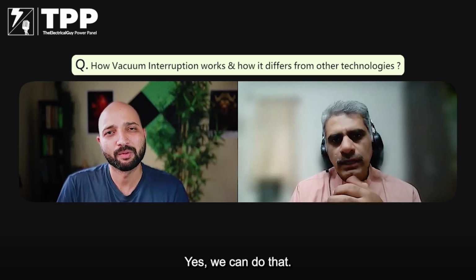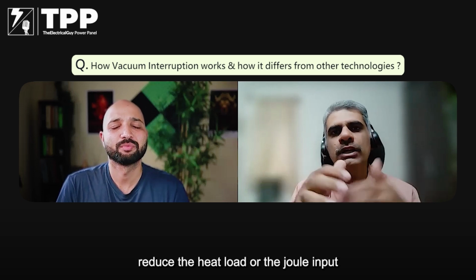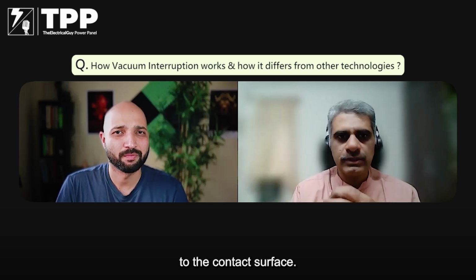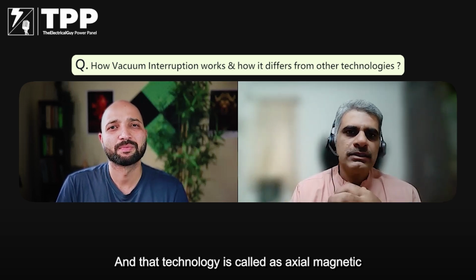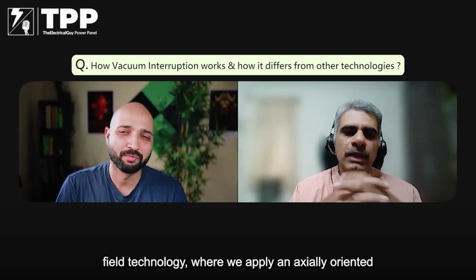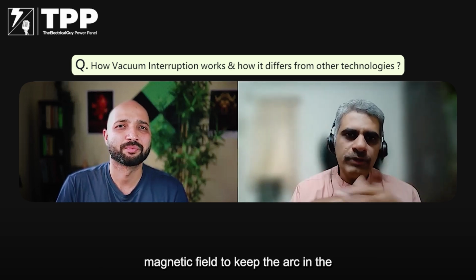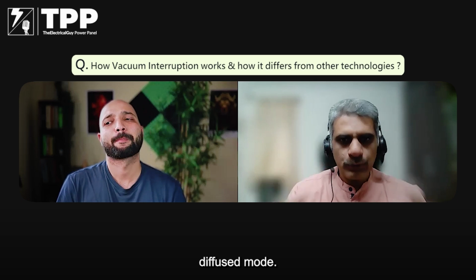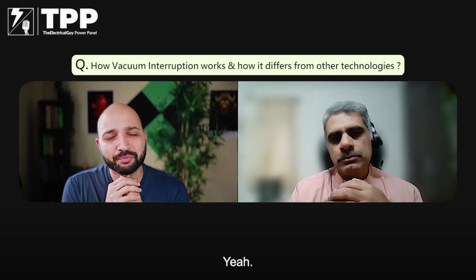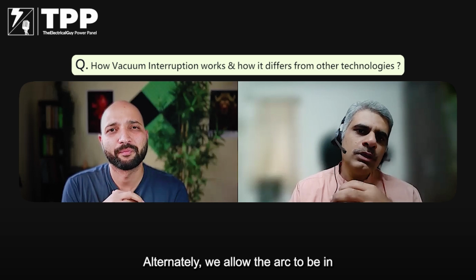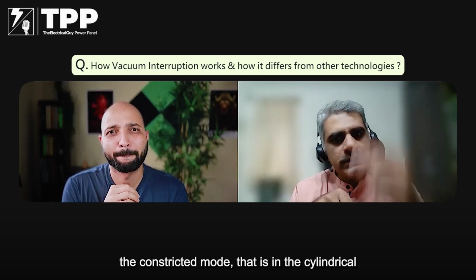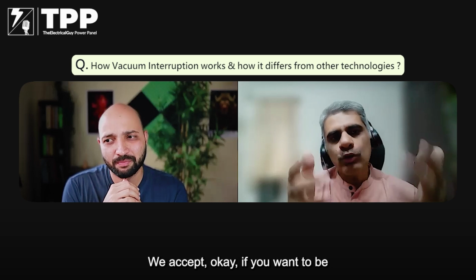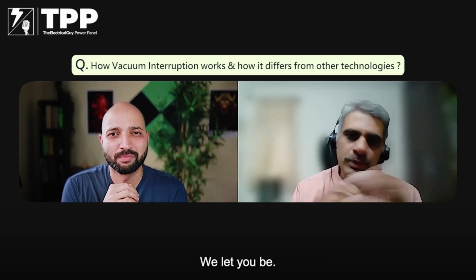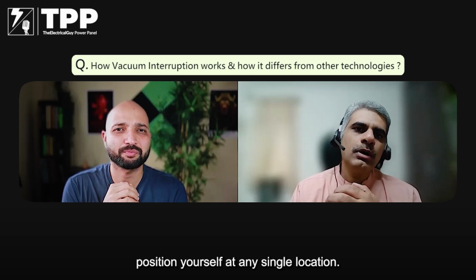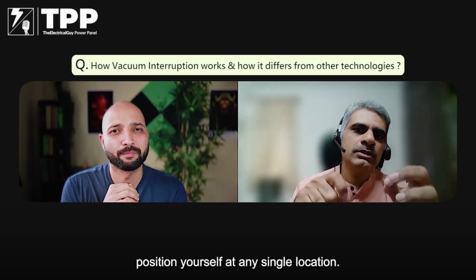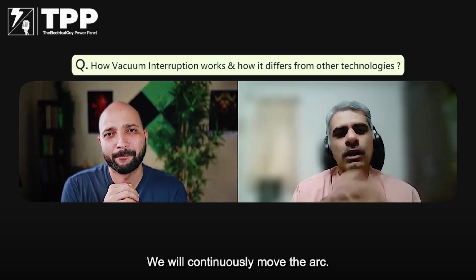Yes, we can do that, and that is one of the ways to reduce the heat load or the joule input to the contact surface. That technology is called the axial magnetic field technology, where we apply an axially oriented magnetic field to keep the arc in the diffused mode. Alternately, we allow the arc to be in the constricted mode, that is, in the cylindrical mode. If you want to be in the cylindrical mode, no problem. We let you be. But then we will not allow you to position yourself at any single location. We will continuously move the arc.